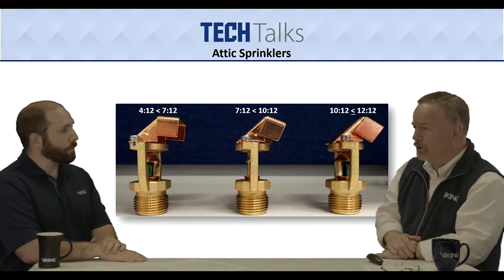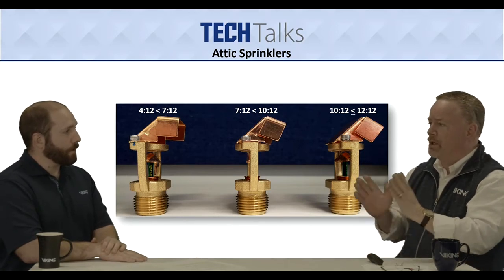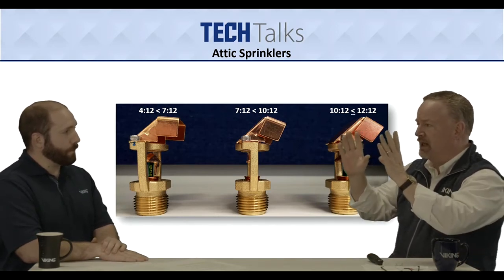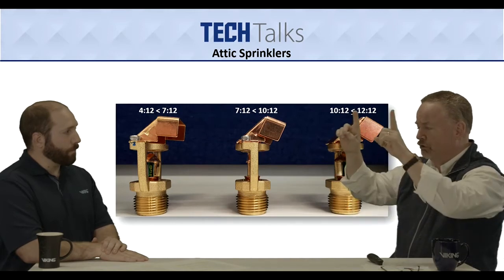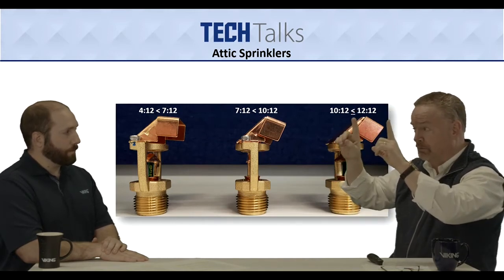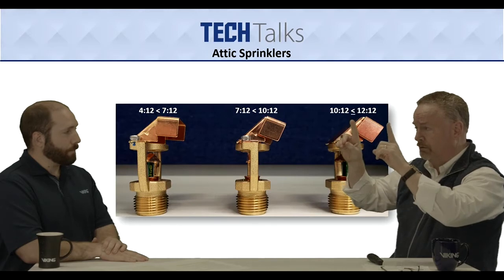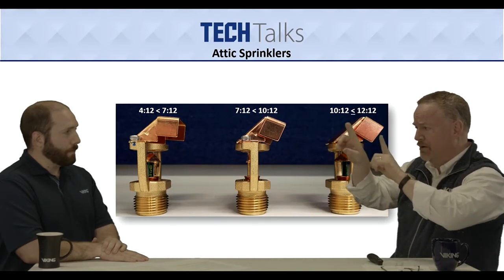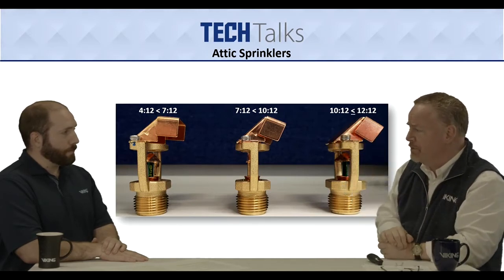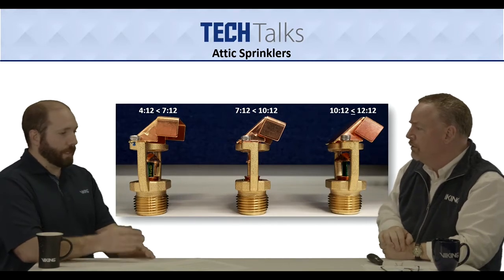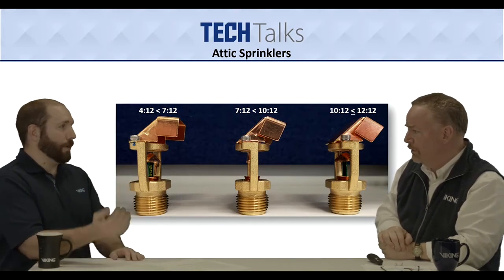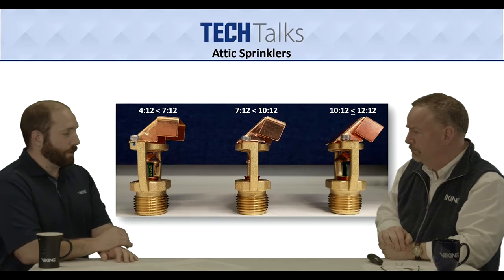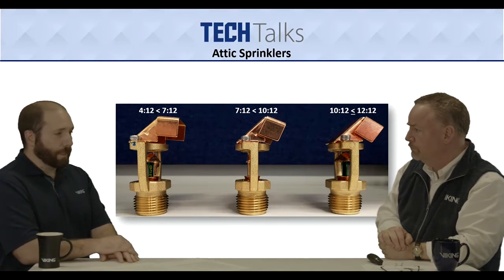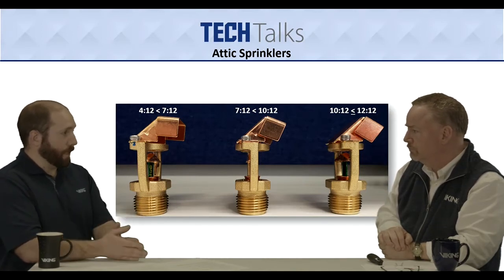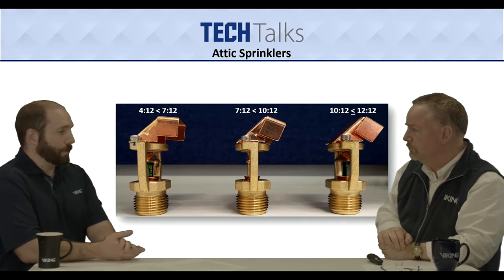Okay, so I'm coming up off that main line. Can I use them really close back to back, or do I have to separate them somehow? Yep, you'd actually separate them with a heat collection baffle behind them. That way they don't cold solder each other. And then they can spray down a single slope and protect multiple slopes.